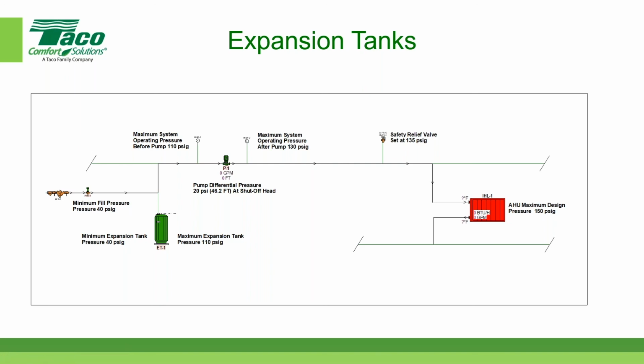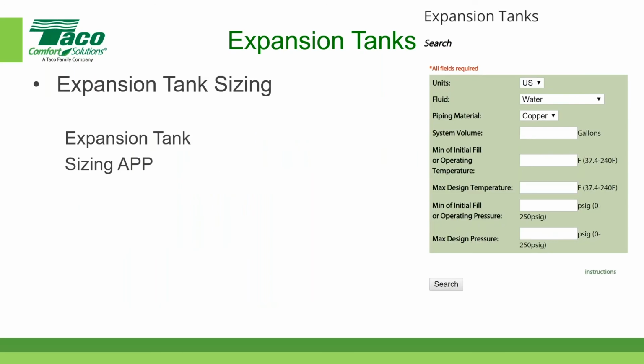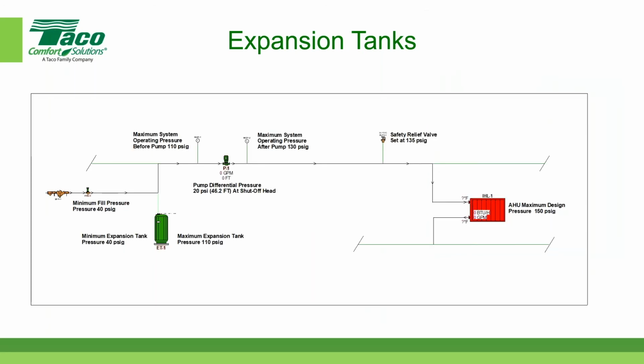Yeah, we have a couple of questions pertaining to chilled water systems. So you did a hot water system. Are the calculations and the methods that you did pretty much the same for a chilled water system and locating the expansion tank? Yes, so for chilled water and hot water, everything is the same except for the temperatures that you choose. So when I'm designing a chilled water system, I pick the same fill temperature of around 50 degrees Fahrenheit, only I pick in this case a different maximum temperature. Even though the chiller might be set at a maximum temperature of 55, I would pick a maximum temperature of around 110 degrees. And the reasoning behind that is simple.